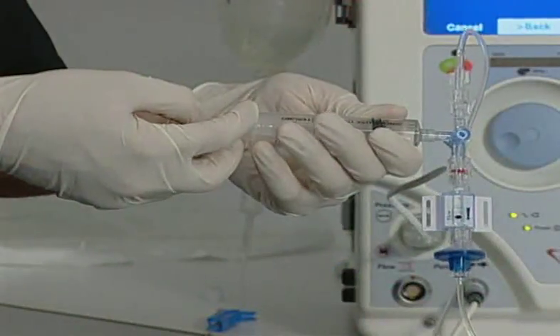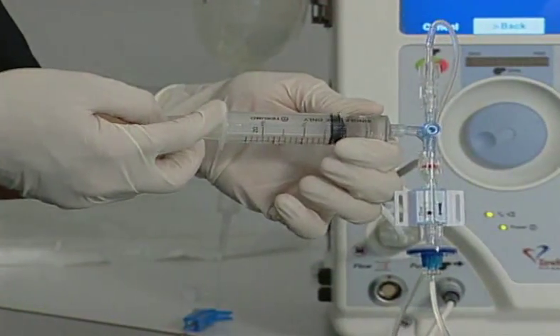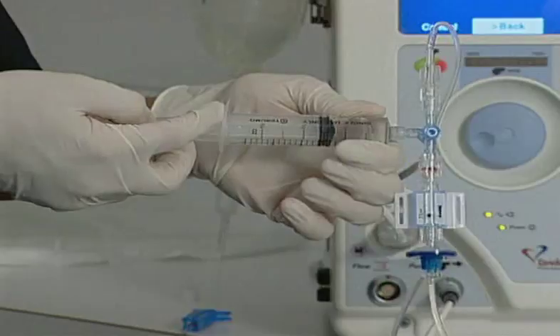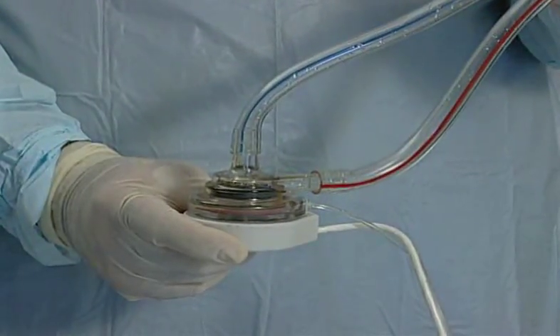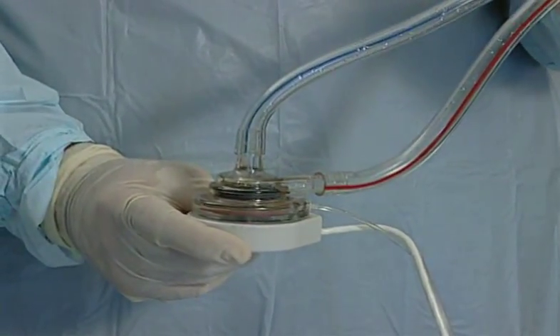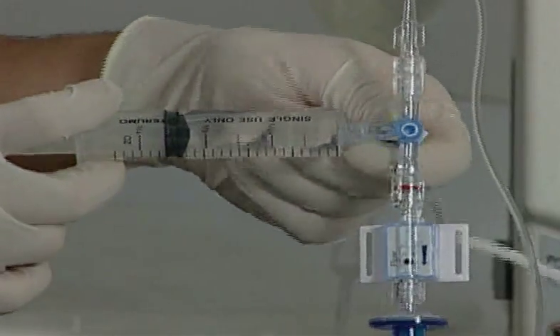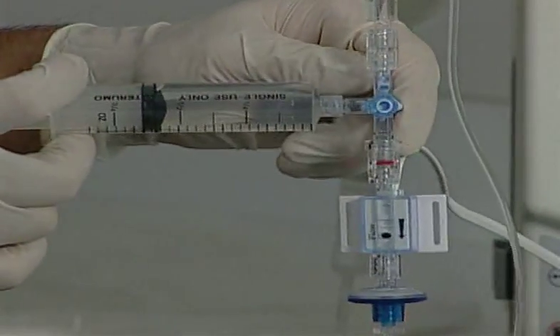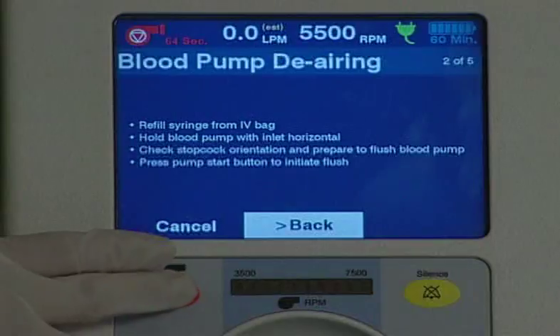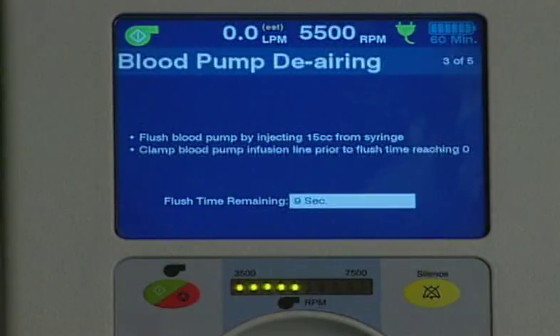The controller operator refills the syringe with heparinized saline from the infusion bag. Hold the pump with the inlet port, blue stripe, horizontal. Turn the stopcock off to the bag while starting to inject the heparinized saline. Then press the pump start-stop button. The pump will automatically run at a speed of 7,000 RPMs for 10 seconds.